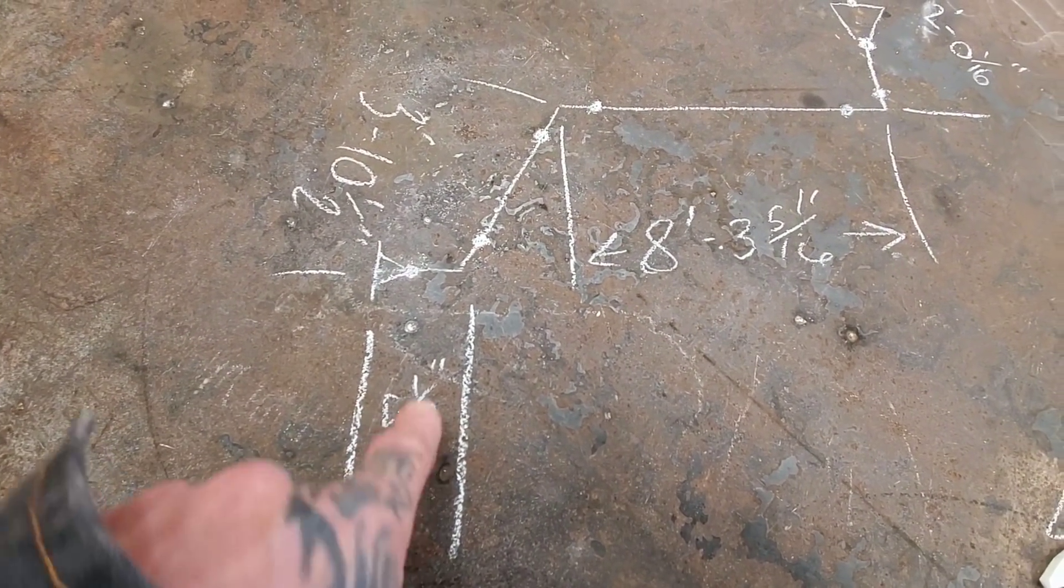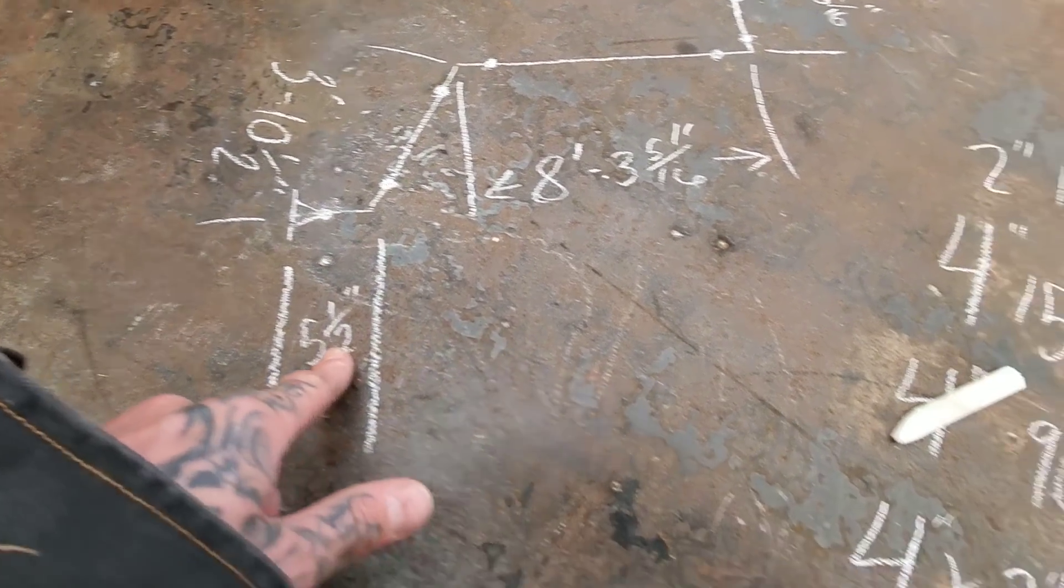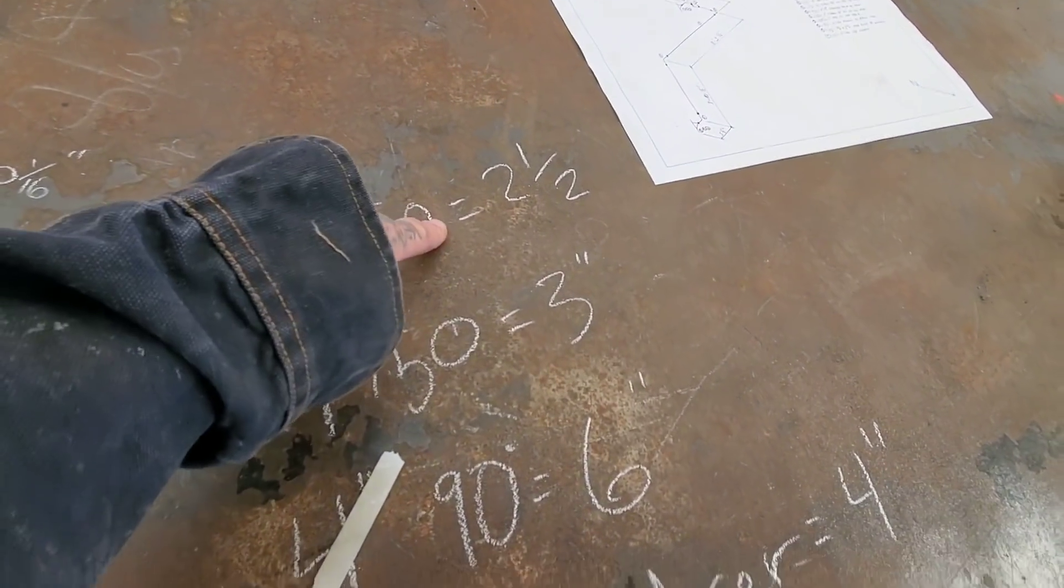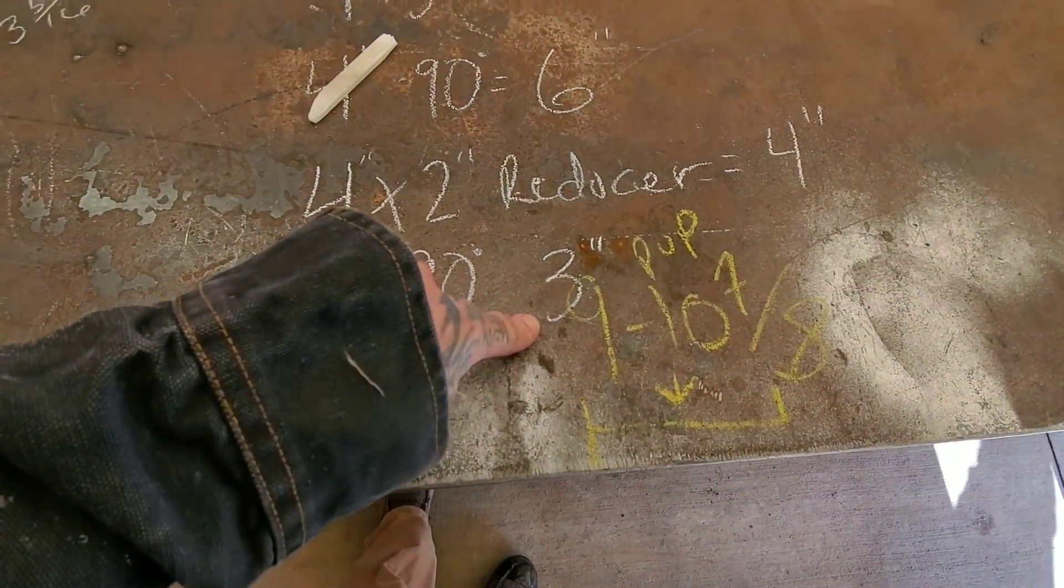This is a two inch 150 plus a two inch 90 long radius equals five and a half inches. So two and a half plus three inches equals five and a half, that's fitting to fitting.